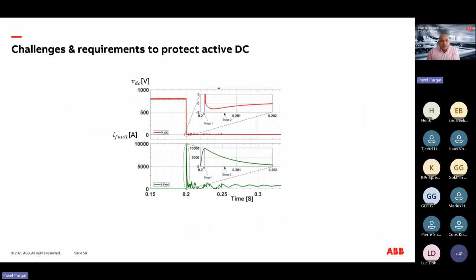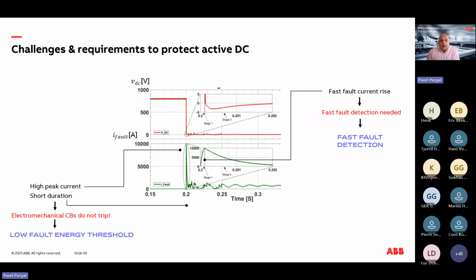As I explained, there are some challenges in the DC system, and just as a recap before we go to the next section, the first problem is that the current is rising very, very fast. So we need to detect the fault quickly, and we need new methods for fault detection. The second problem is that we reach the peak current very quickly, and if the capacitor is the only source of the energy, the voltage will drop. So we have a low fault energy threshold. When the voltage is dropping and we don't stop it, we will have a blackout. So we need to interrupt the fault very fast.